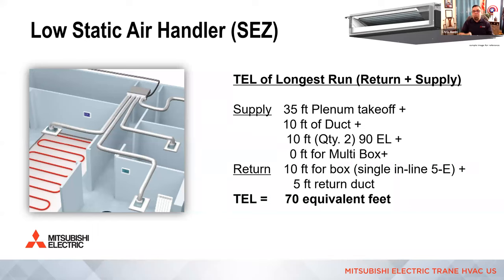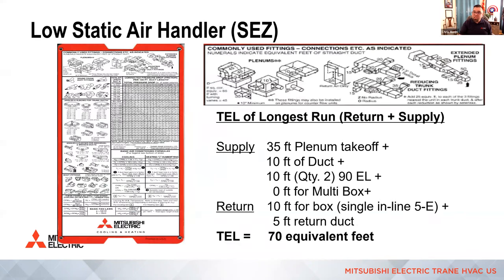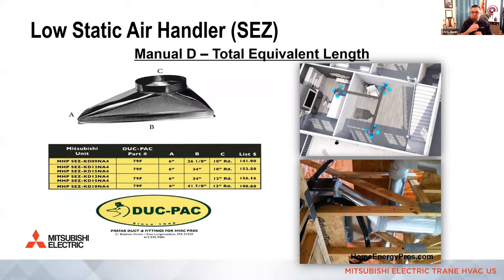All right. When you add up all of these values, it ends up being 70 equivalent feet. And when you do this with a low static air handler, you want to be sure that this value is below 100. If it's above 100, we're going to actually do the math and it'll reduce the values of the friction rate even further from what we have for available static. So these were the pictures I was telling you about. Actually, I probably should have brought this up earlier. I apologize. But on the back of duct calculators, these are those fitting values I was referring to. All right. So when we do this layout, it's really important for the air to make smooth transitions.